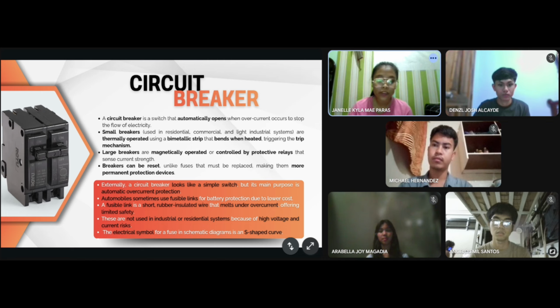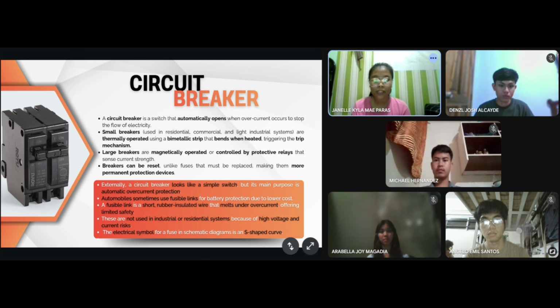Unlike fuses that must be replaced after blowing, circuit breakers can be reset, making them more permanent and convenient protection devices. Externally, a circuit breaker may look like a simple switch, but its main purpose is automatic overcurrent protection. Automobiles sometimes use fusible links for battery protection due to lower costs, but these offer limited safety. Circuit breakers are preferred in industrial and residential systems because they provide reliable protection against high voltage and current risks.